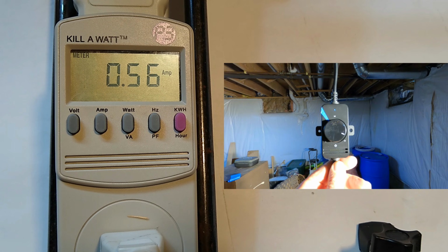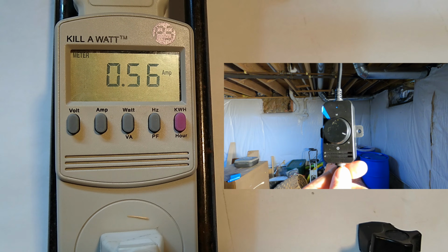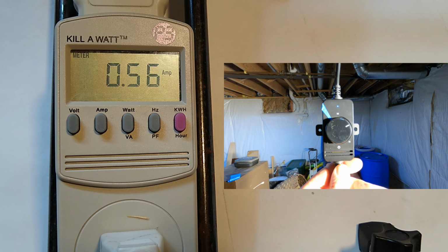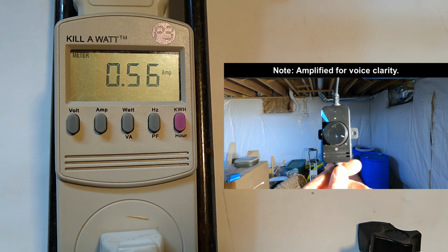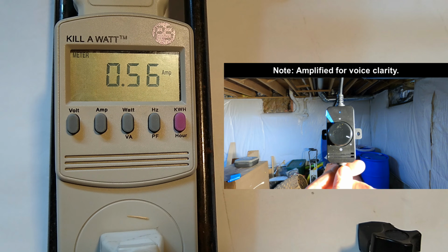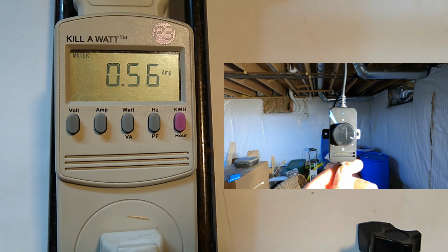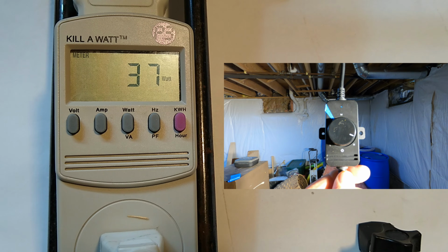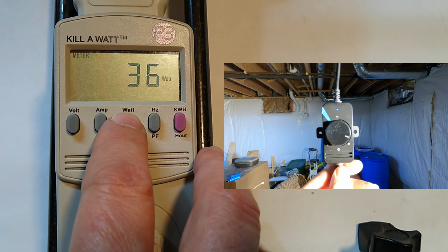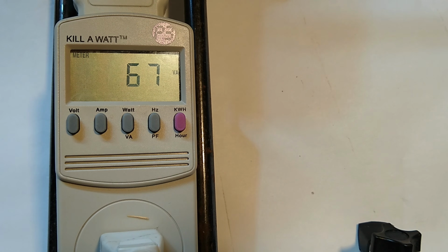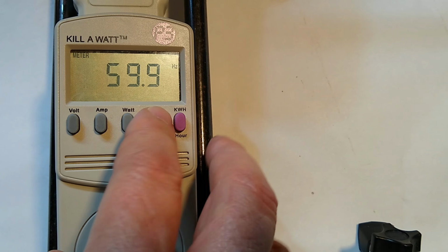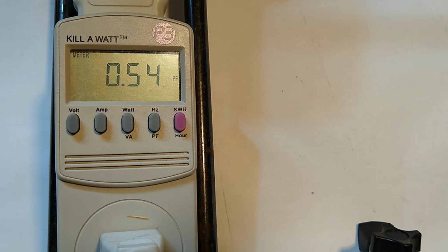Okay, so now I set the duct booster to 100% speed. That's the high mark. As far as it goes, that's high speed. The current draw is 0.56 amps. It's using 37 watts of power at 67 volt amps. And the power factor is 0.54.